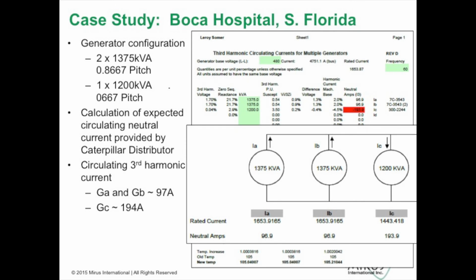The second case study is a hospital in South Florida, again with backup generators. The generator manufacturer provided calculations to show what they expected the neutral circulating current to be. In this case, it was the same generator manufacturer, but the generator manufacturer no longer provides the same pitch configurations. So the two existing were 0.8667 pitch, and the new generator that they had to purchase was a 2/3 pitch. I apologize for the typo here. That should be 0.667. That's a 2/3 pitch generator.